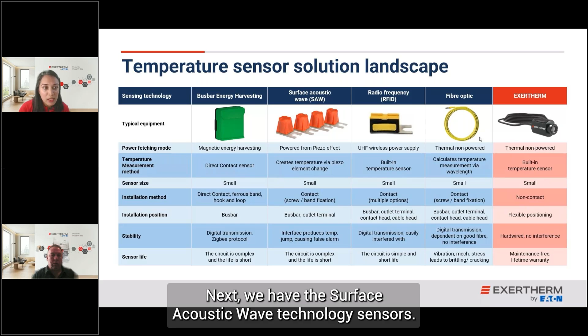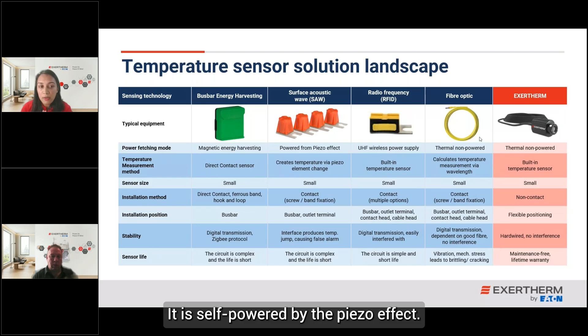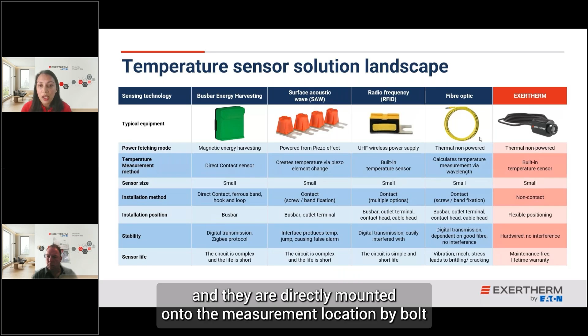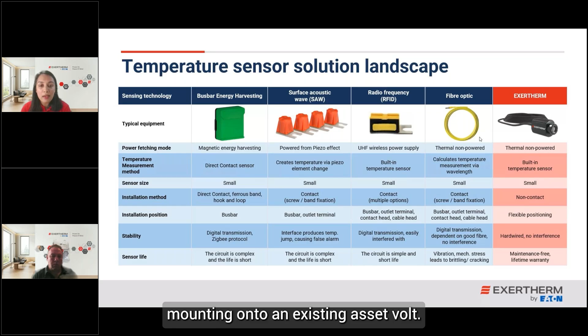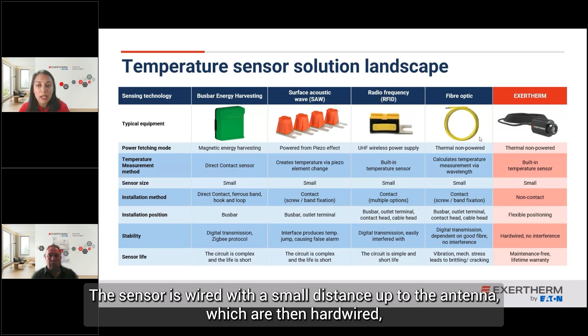Next, we have the surface acoustic wave technology sensors. The sensor is small and self-powered by the piezo effect. The temperature reading is generated via piezo element change, and they're directly mounted onto the measurement location by bolt mounting onto an existing asset bolt. Radio frequency signals are used between monitoring units and sensors to transmit and determine temperature. The sensor is wired with a small distance up to the antenna, which is then hardwired. Also, the number of sensors is limited by the number of frequencies, and a temperature jump due to an interface introduction can cause false alarms.